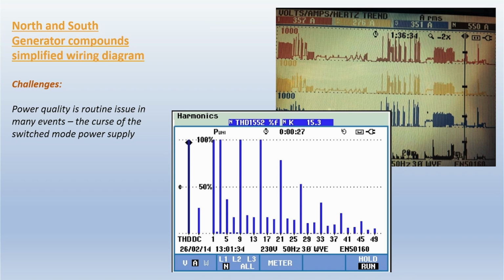So power quality is a really big issue now. The bottom graph shows the harmonic spectrum of the neutral current. I can't remember what the fundamental frequency was on this, but you can see the real prevalence of third harmonics, so the third, ninth, the triplens - third, ninth, fifteenth. Those are the ones that really add up in the neutral itself.